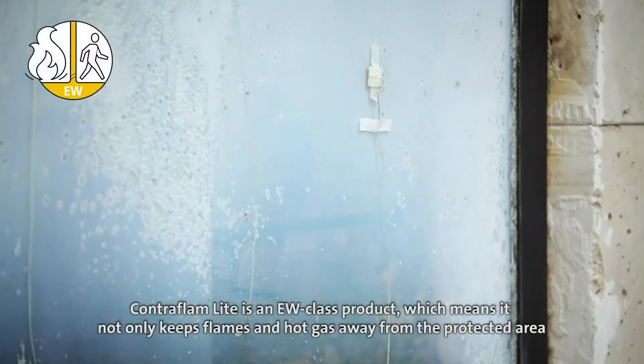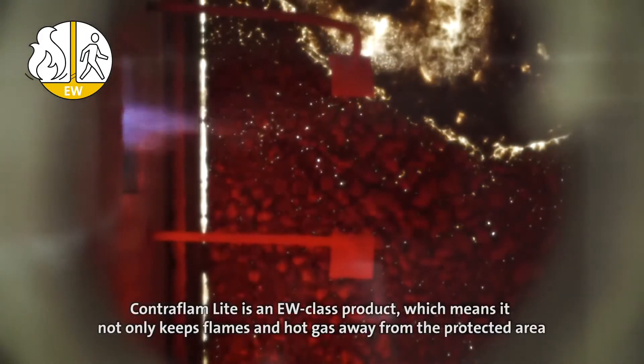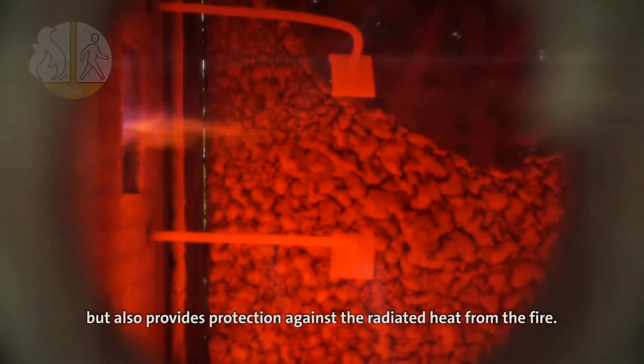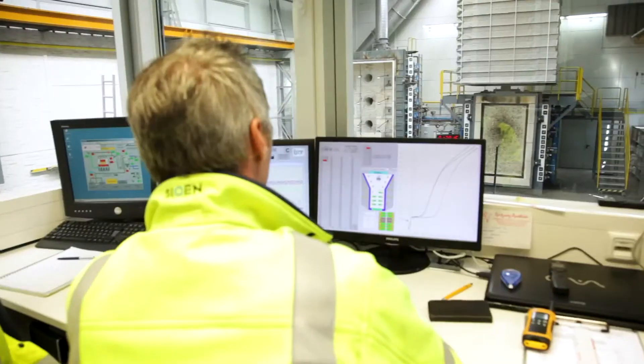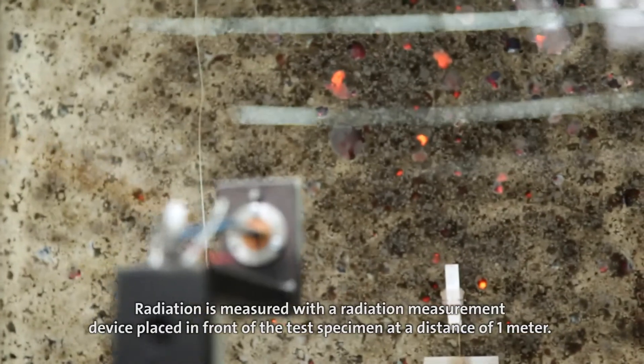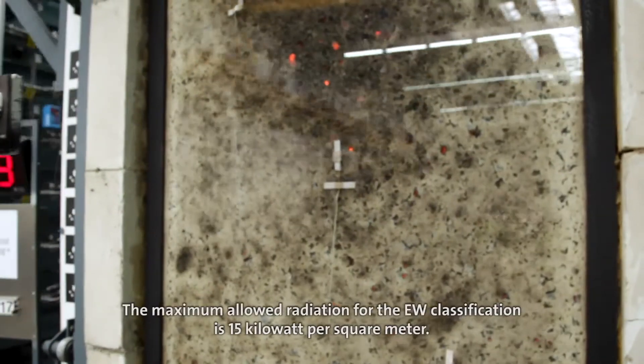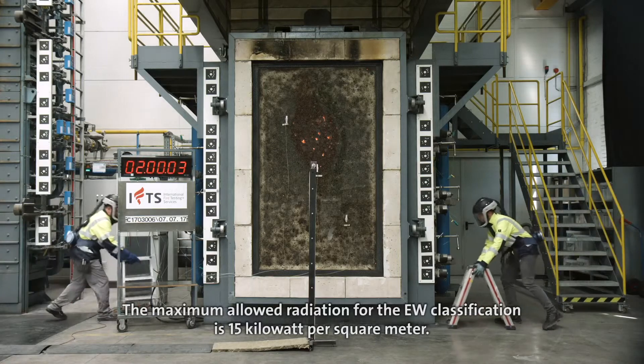Contraflam Lite is an EW class product, which means it not only keeps flames and hot gas away from the protected area but also provides protection against radiated heat from the fire. Radiation is measured with a radiation measurement device placed in front of the test specimen at a distance of 1 meter. The maximum allowed radiation for the EW classification is 15 kilowatt per square meter.